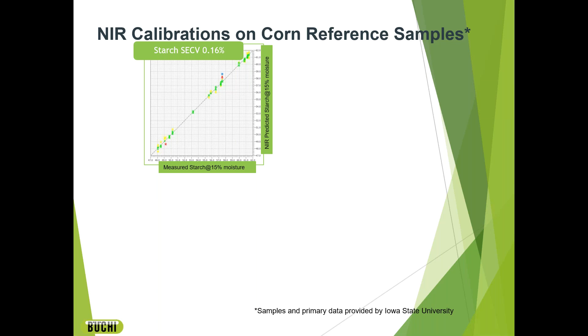So it shows us that what we're able to do is to replicate what the primary method is doing, only, as we mentioned, in a very fast and even continuous measurement online. But we don't stop there. We can do multiple analyses simultaneously, provided that we have the corresponding calibration curves for each of these, which in this case, we're showing the protein, which of course will be the important one in terms of the DDGS byproducts, fat, which again could be a potential source of revenue, and then also moisture in the final product.